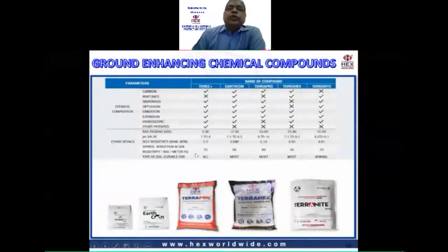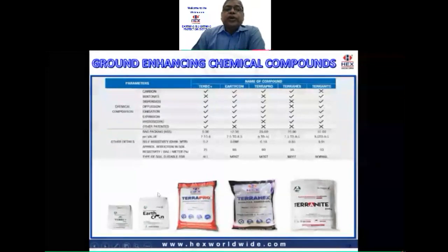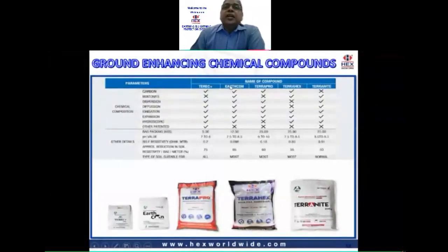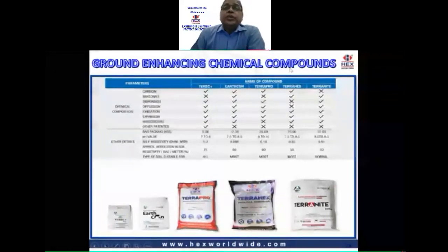Now, this can be used for all soil conditions, but we recommend it to be used mostly in harsh or rocky soil conditions, where it has proved itself to the satisfaction of our customers. Then we have EarthCon, which comes in a 12.5 kg pack. This is a blend of bentonite and carbon, and it has been tested for a self-resistivity of 0.098 ohm meter. And it can be used in most soil conditions very effectively. We have used it. It reduces the surrounding soil resistivity by about 65%.